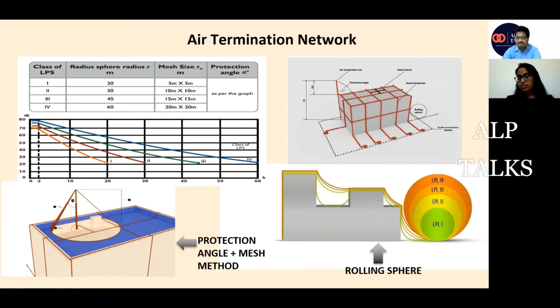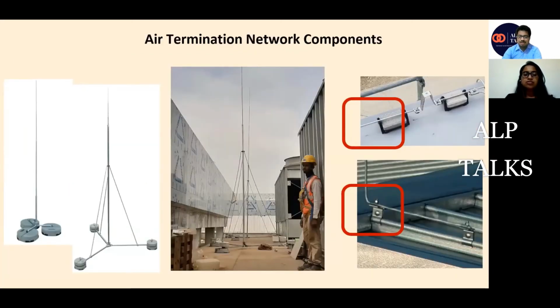Can I change the slide? These are the types of air terminals we generally use. These are known as self-supporting air terminals. When we have equipment installed over the roof, like cooling towers and chillers, we cannot install the air terminal directly on that equipment. So at that time we use these self-supporting air terminals. These should be installed at the side of the equipment, and they will protect the equipment or any other structure of my roof from lightning strikes.